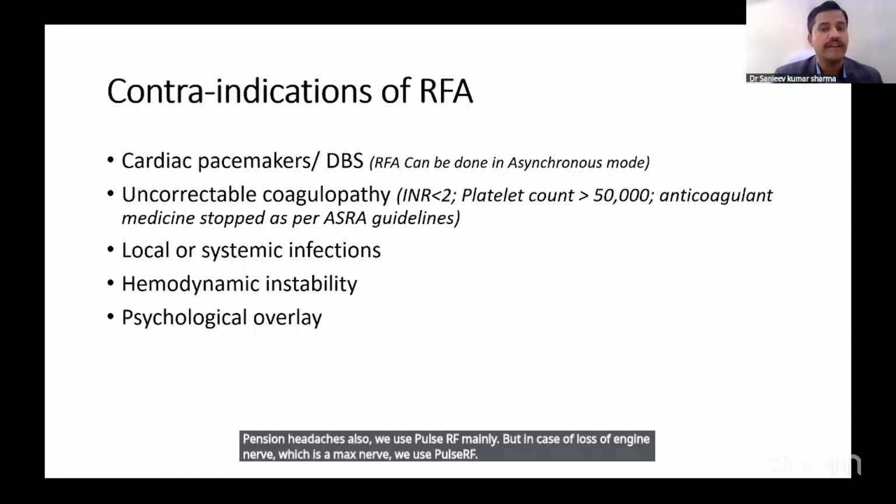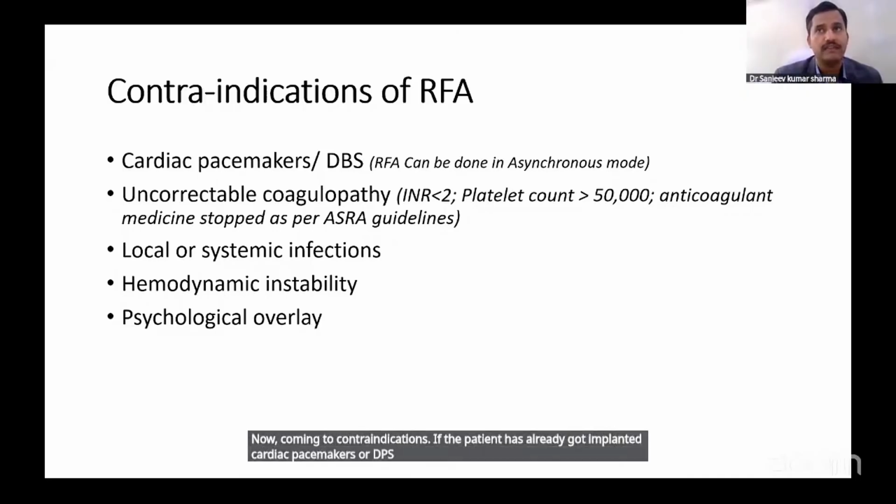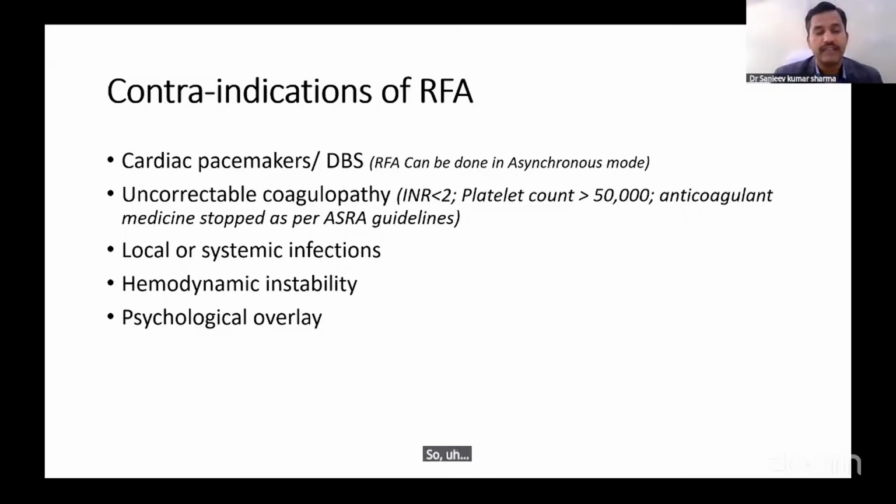Now coming to contraindications. If the patient already has implanted cardiac pacemakers or DBS, their functioning can be hampered with the use of RFA because electromagnetic fields are created by RFA. RFA can be done if these devices are put on asynchronous mode.